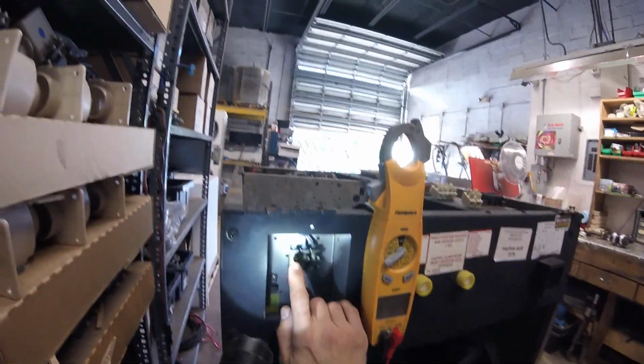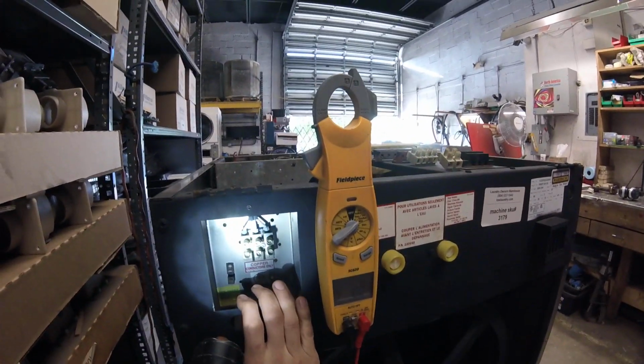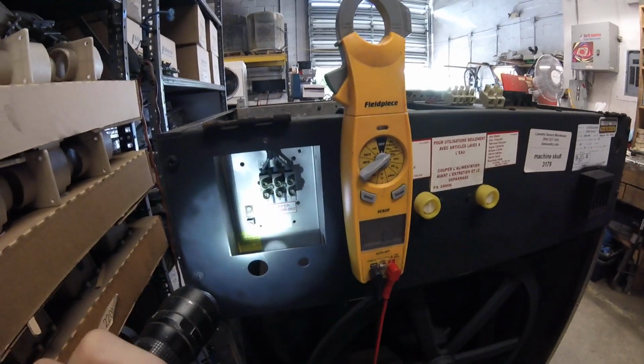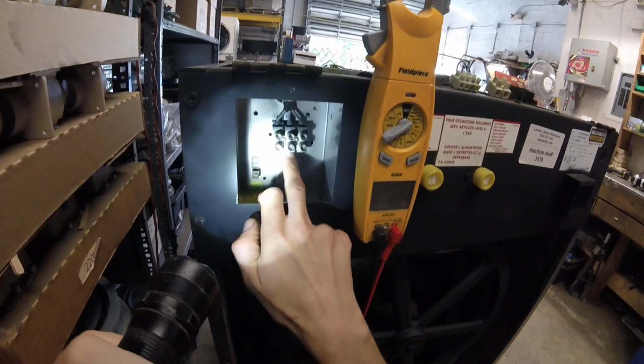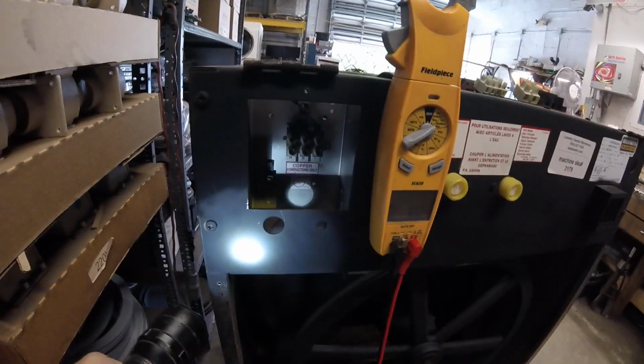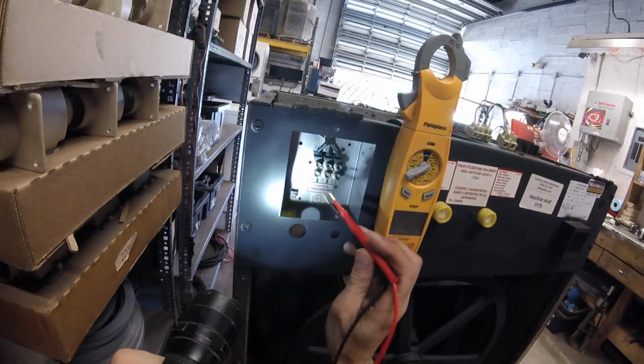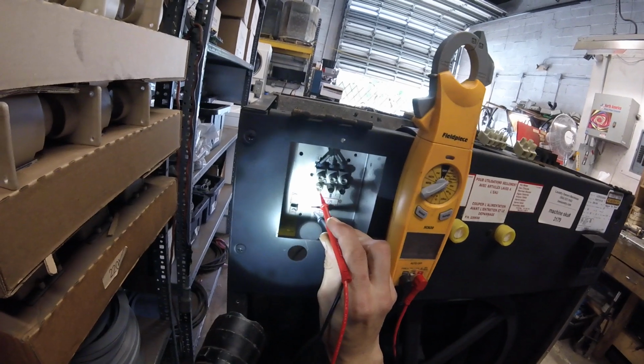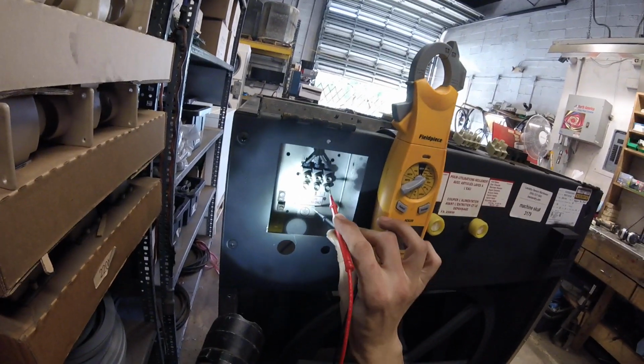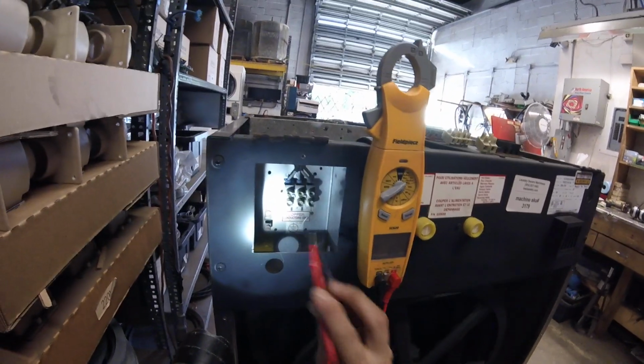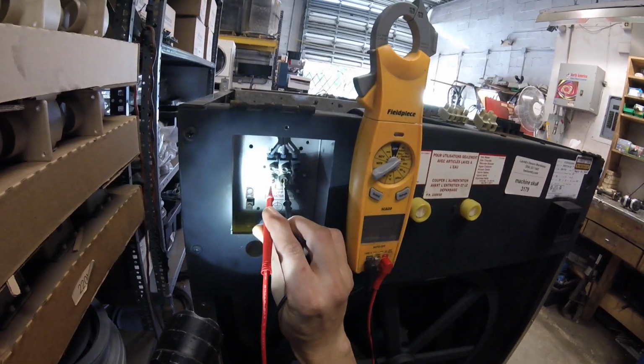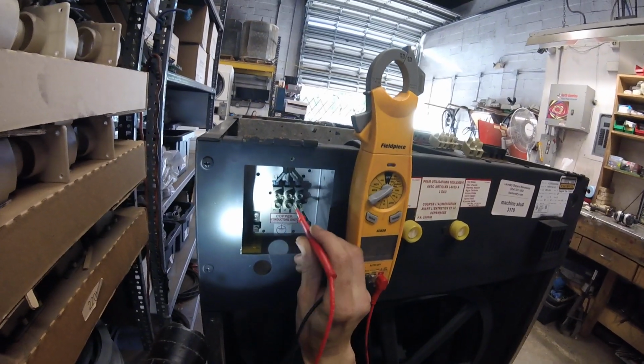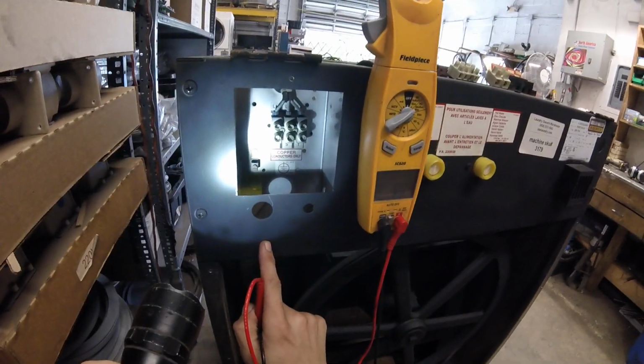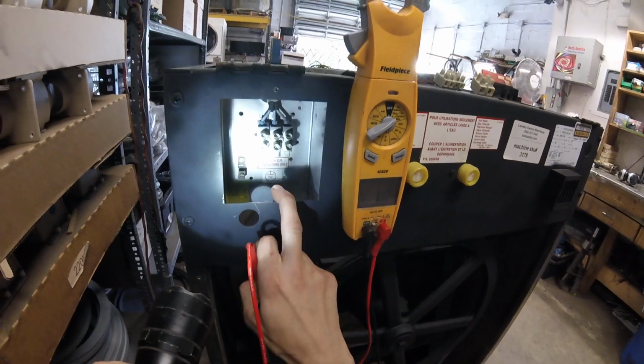So over here at the power terminal, it's going to be labeled L1, L2, and L3 for the hot legs, and you have your fourth ground here. Now, once you have your three hot legs installed with your voltmeter, you should be reading 110 volts from L1 to ground, L2 to ground, and L3 to ground. When you read across L1 and L2, you should be getting 220. Same with L2 to L3. So individual legs to ground, 120. Legs jumped across should be 220.